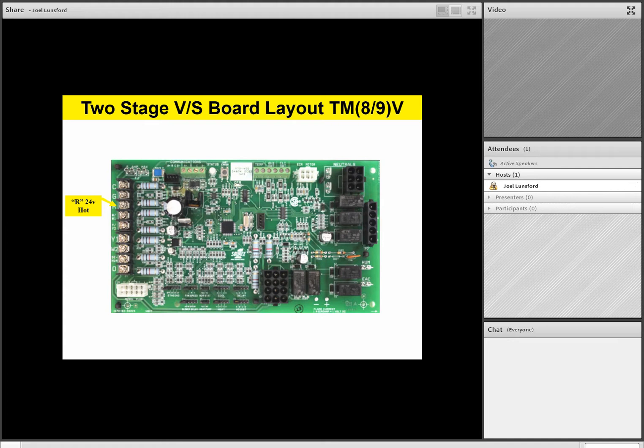W1 is first stage heating call. Y/Y2 is second stage cooling call. So this is a two-stage heating, two-stage cooling capable board. Y1 is our first stage cooling call. W2 is our second stage heating call.